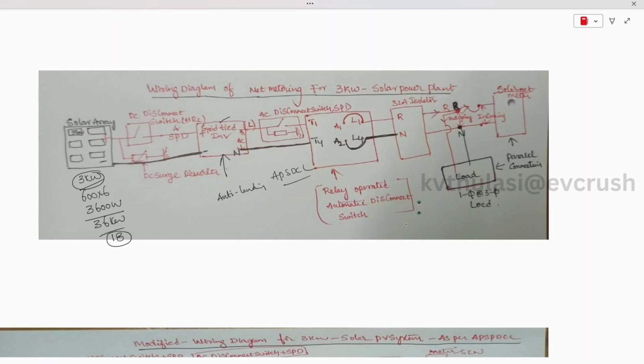So we have to connect this to terminal 1 and terminal 4, and the line output is nothing but L1 and L4. So this L1 and L4 we are going to connect to an isolator, and the output of the isolator we are going to connect with the help of a fuse at the output of the meter.